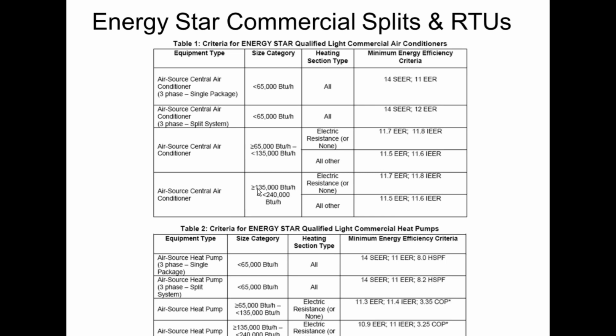The bigger units above 135,000 BTUs have the exact same specification. So I have no idea why they made them into two tables, other than the fact that maybe they were different at one point in time. But right now they're exactly the same. So same spec. And then heat pumps are down below. Works very similarly. Plus you have to have a heating rating in addition to the cooling. So on the small stuff, you have to have an HSPF. The big stuff, you have to have a COP rating in order for those to qualify.